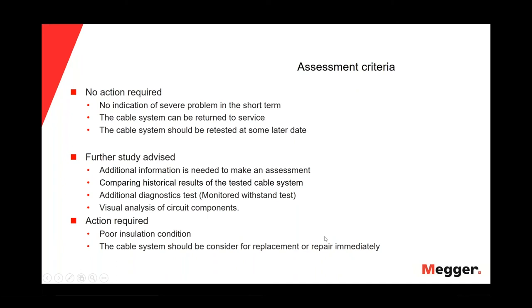Something that I would like to say is that if we do a tan delta test for the first time on an old cable and the result we get is action required, we will not recommend replacing the cable. Maybe we should do additional measurements, or maybe do a visual analysis, and maybe repeat the tan delta test in 1 year to see if we have variations in the values of the delta of the tan delta, or the deviation, the standard deviation, okay?